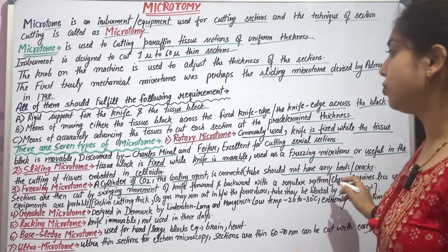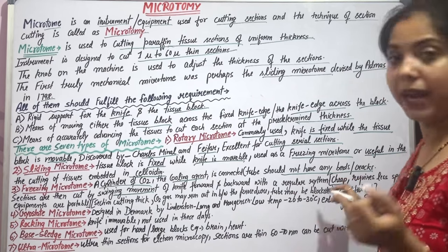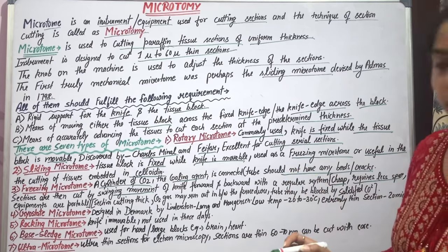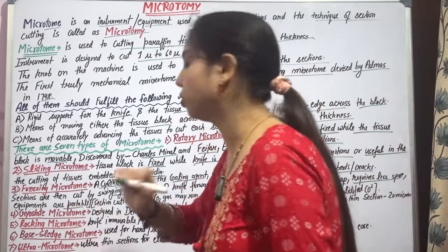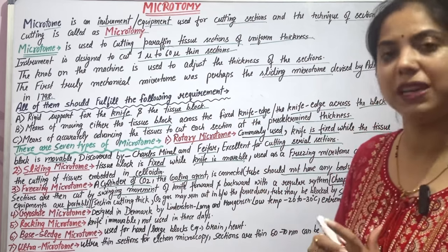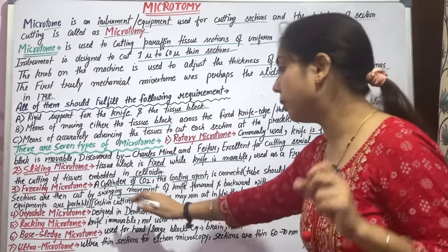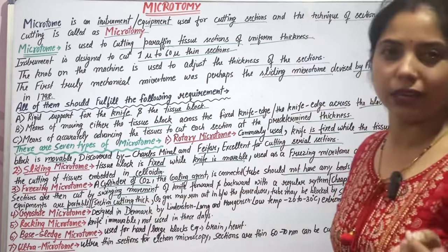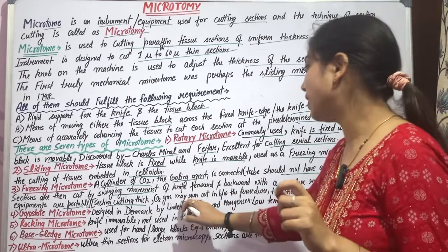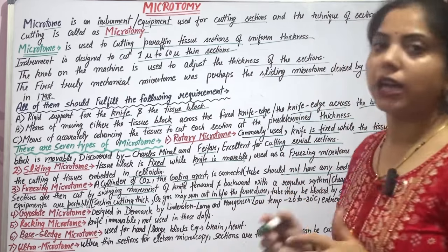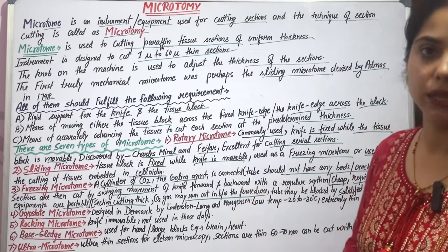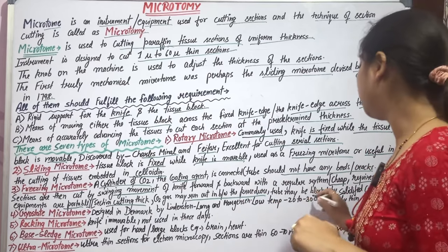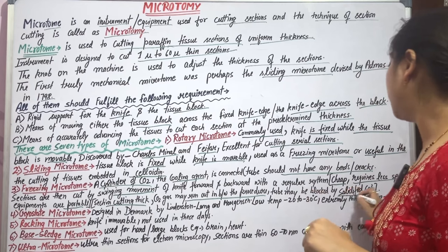The advantages of the freezing microtome are that it is cheap, requires less space, and the equipment is portable. The disadvantages include sections being uneven in thickness, CO2 gas may run out mid-process, the tube may leak, and the tube may be blocked by solidified CO2.